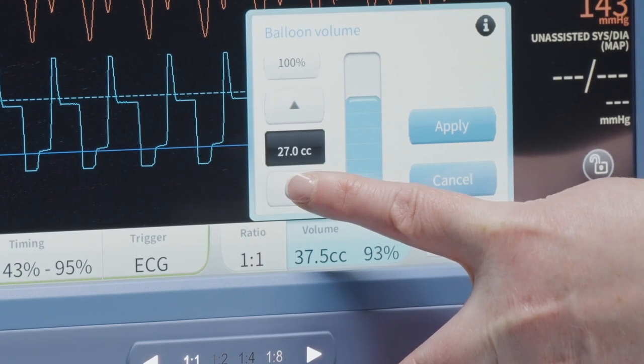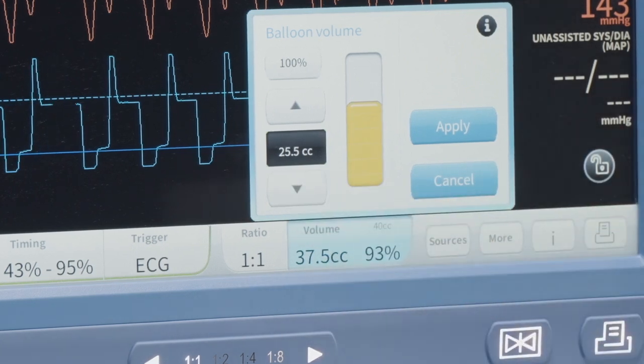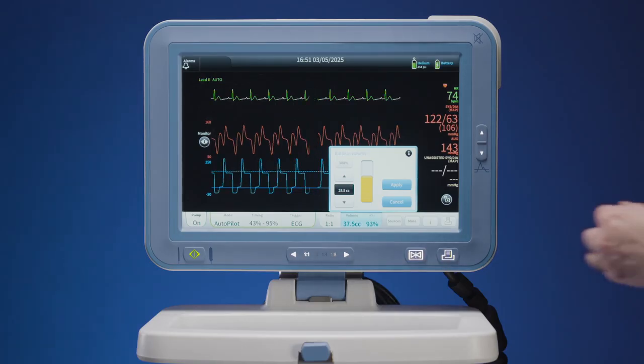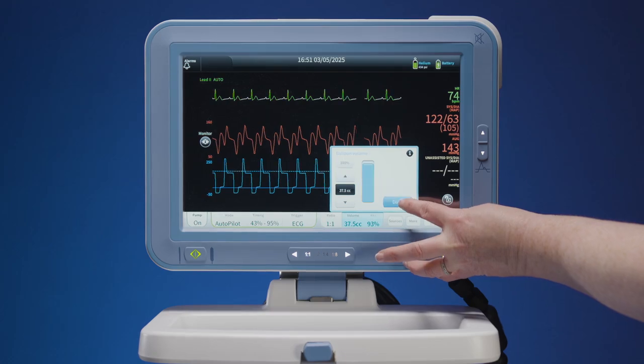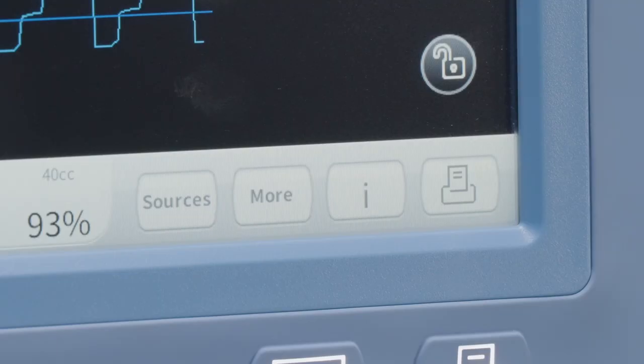If this is done, the volume bar will change to yellow to indicate that the volume is below the recommended setting. There are 4 other IABP control keys on the action bar. The AC3 Optimus IABP has a Sources key to select and change the ECG and AP sources and functions, a More key to select more advanced settings, an I key to access help on specific functions, and a printer key to start and stop a recording strip.